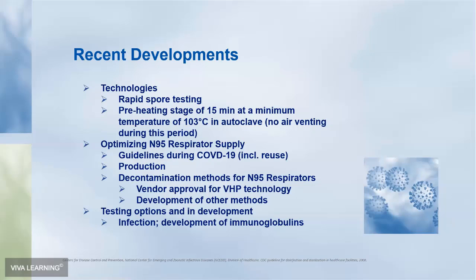So, recent developments. There have been quite a lot of recent developments. If we start with technologies, we just talked about increasingly rapid spore testing. There's now an option in one series with a preheating stage of 15 minutes at a minimum temperature of 103 degrees C. This is a new addition from Tuttnauer. During that initial period there's no air venting, so it reduces microbial load. It's conducted at a sufficiently high temperature that it would kill viruses and also other microorganisms. So it's not rendering anything sterile. You still need to run the sterilization phase, but it does help to reduce microbial load.